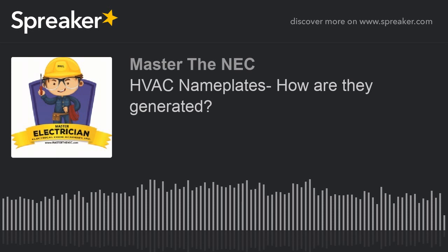Now, what about the compressor conductors? That's the compressor, that's the largest. So that one was 125% of 26 amps, which is the full load current, and that equals 32.5 amperes. So that's an 8 gauge that's supplying that.